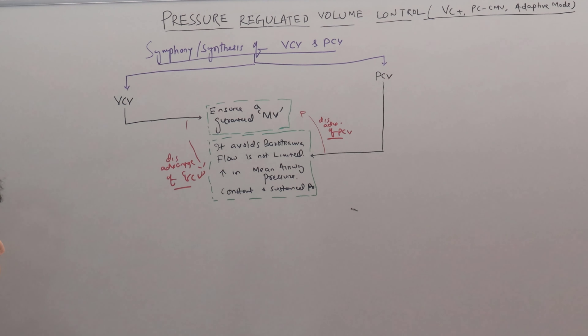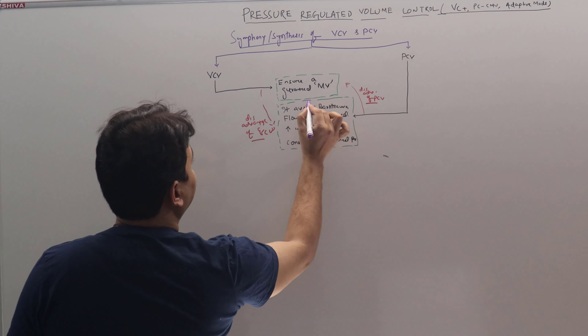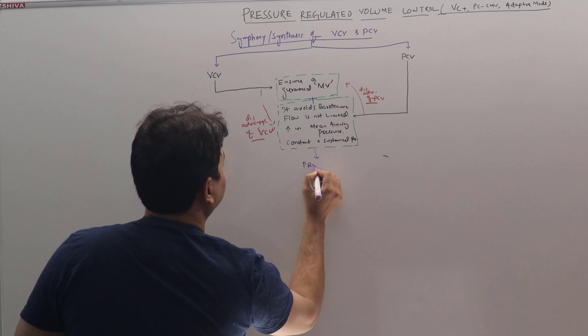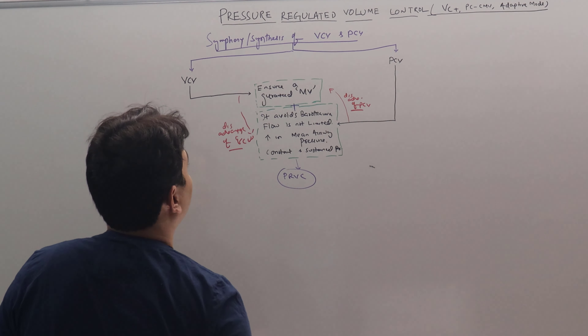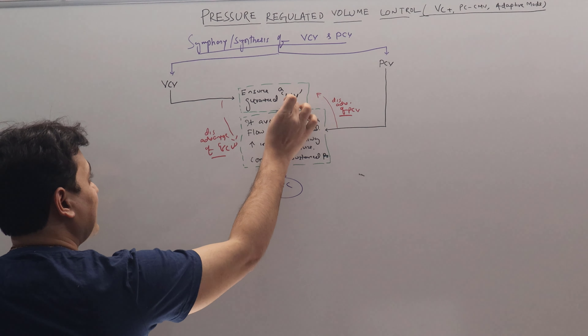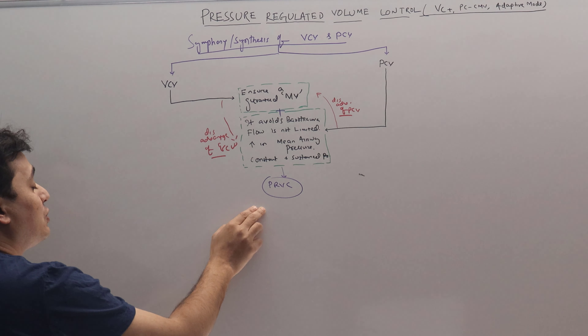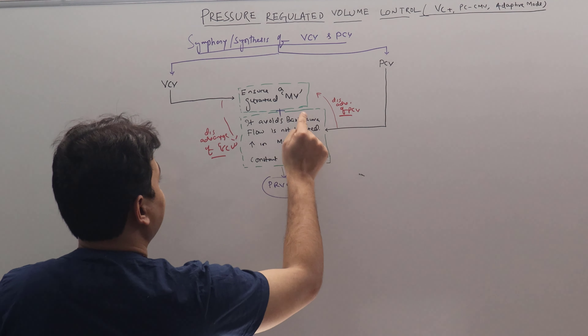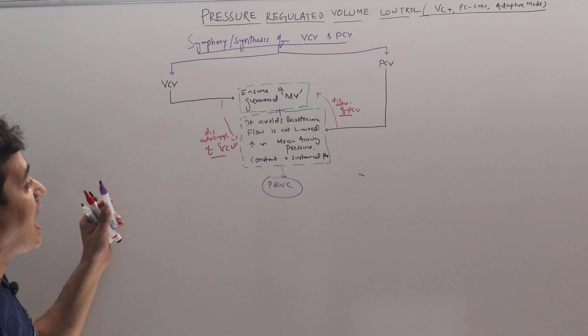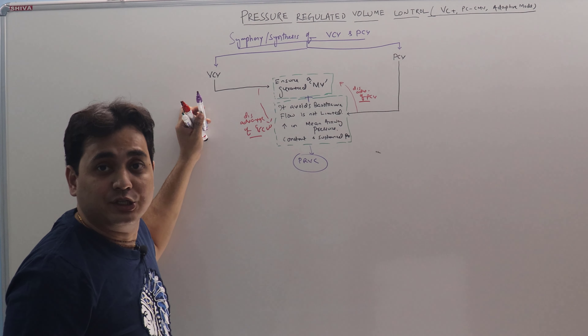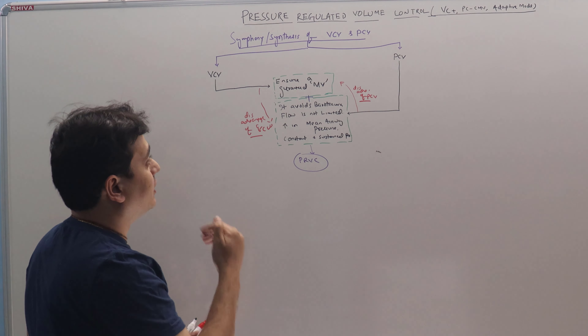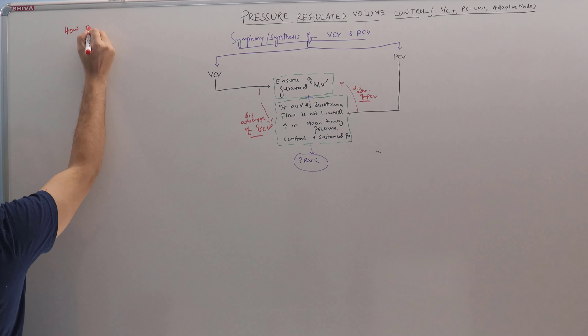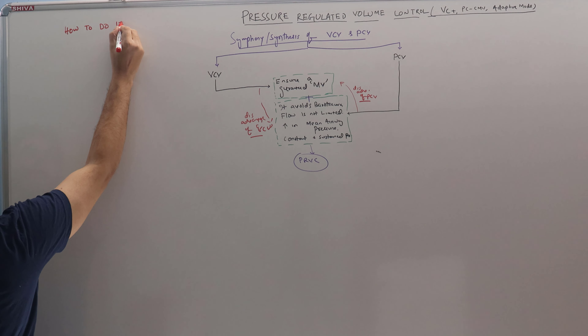So if we combine these two things, this is called PRVC. PRVC will provide a guaranteed minute ventilation, and at the same time it will provide the benefit of a pressure control breath as we have discussed. So now we have discussed what it is. Now we will discuss how it is done.